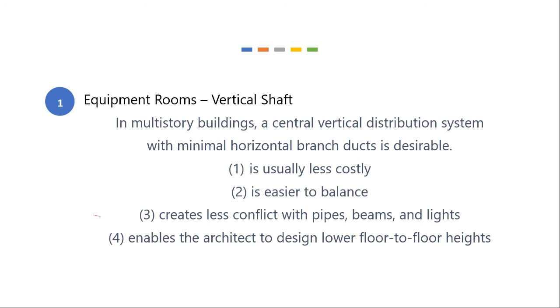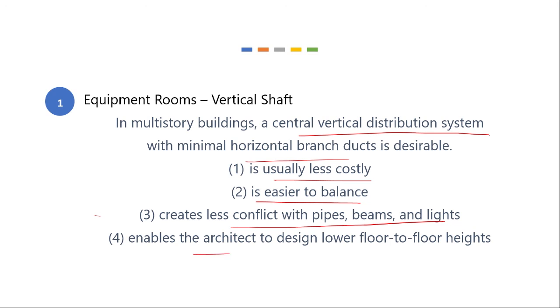So, in a multi-story building, having the vertical distribution system with very few ducts is desirable. It's cheaper. It's easier to balance. There's less conflict with pipes, beams, and lights, and since we don't have too much horizontal system, we can make our floor to floor heights much smaller. So a 100-foot tall building could have 20 floors instead of 15, because every floor can be smaller, because we don't have all this wasted space between the floors where we have to fit in our HVAC equipment.